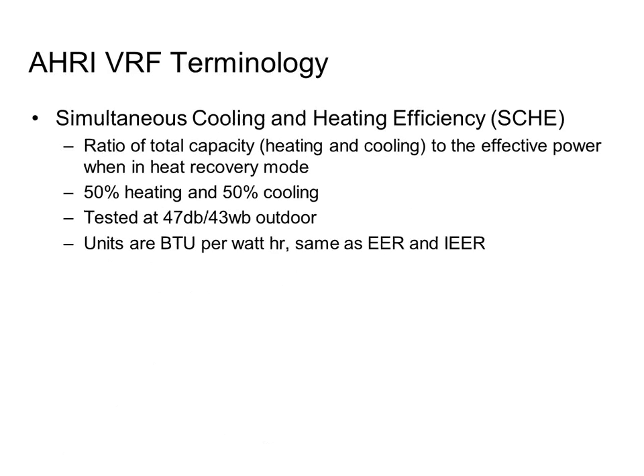Andrew asks if the outdoor temperature matters in the 50-50 scenario. And to be quite honest, until you asked that question, Andrew, I never really thought about it. But you're right. If I have 50% of my zones in heating and 50% of my BTUs going into cooling and nothing's really going to the outdoor coil, it doesn't really matter. I guess it only matters slightly for whatever distance of piping I have sitting on the roof and the heat of the compressor itself. Other than that, it probably doesn't really matter. So you really don't need to test it at multiple outdoor conditions. That's a good point. I never thought of it that way, Andrew.